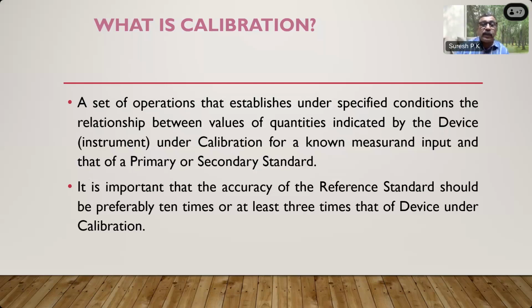It is important that the accuracy of the reference standard should preferably be 10 times, or at least 3 times, that of the device under calibration. 10 times is not very practical in the case of flow measurement, or any measurement. So you try to achieve at least 2 to 3 times better than the instrument under calibration.